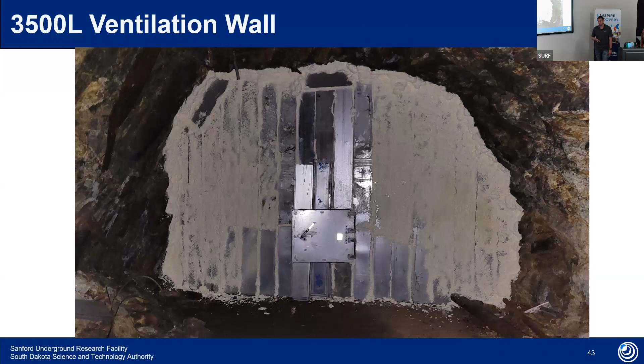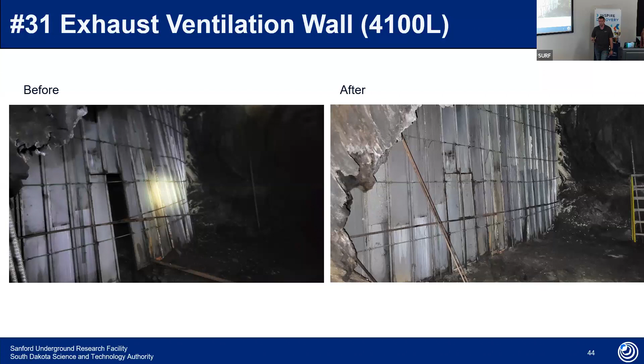Another example is on the 31 exhaust on the 4,100 level. The picture on the left was after a blast on our bypass direct excavation. When we closed the blast doors, the fan was still on, which pulled this wall apart and short-circuited their exhaust system. We went in, determined the cause, and installed a new one, reinforcing it so it wouldn't happen again.